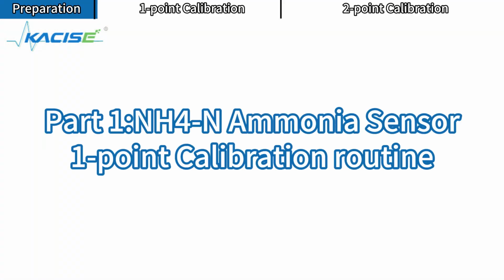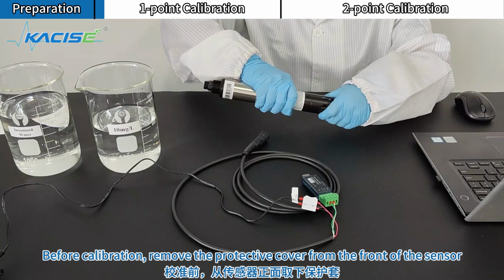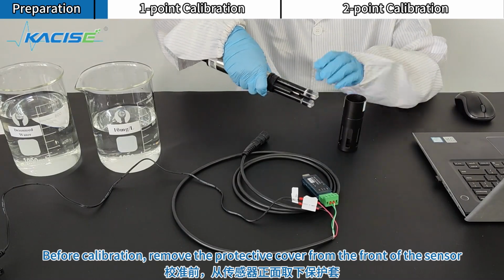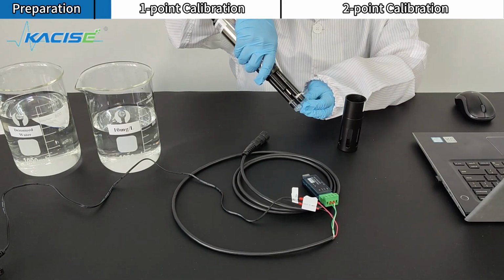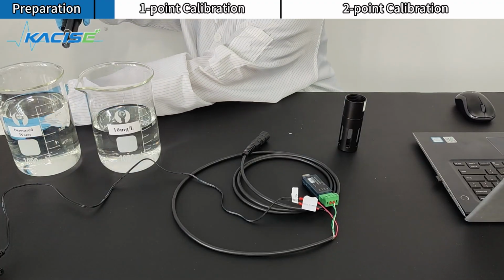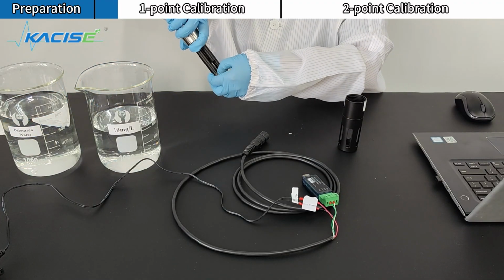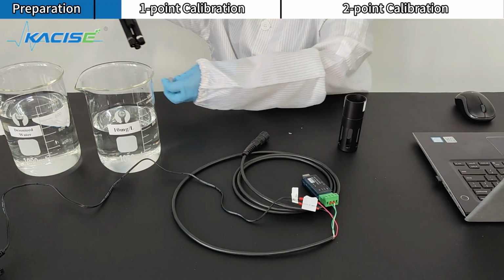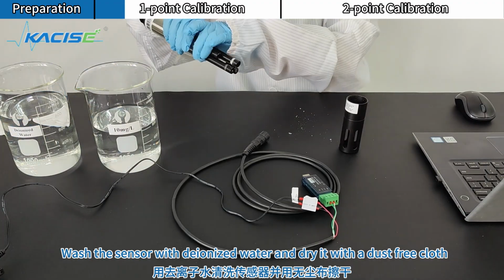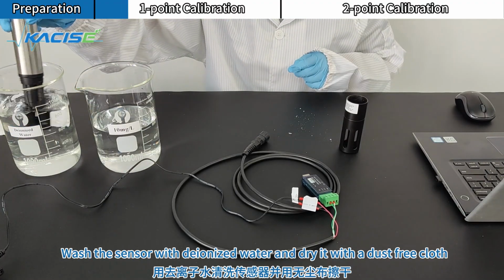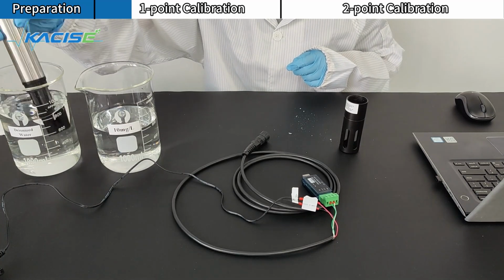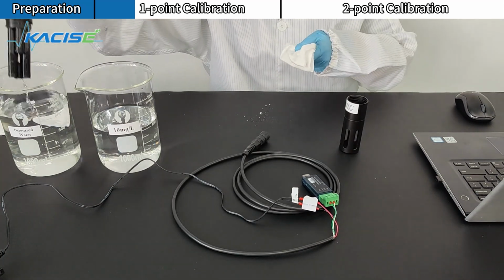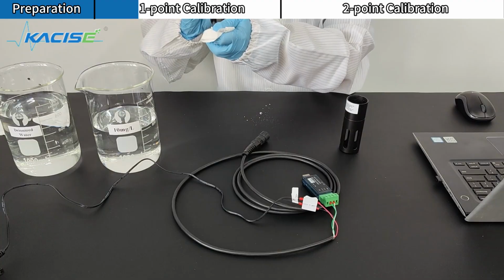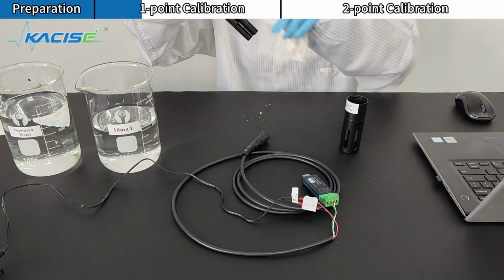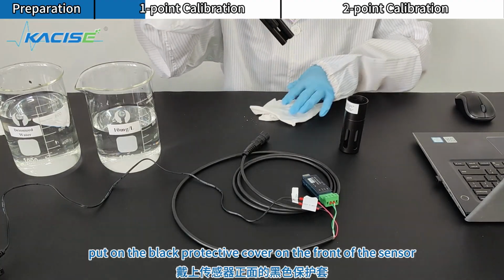Part 1, NH₄-N Ammonia sensor. 1-point calibration routine. Before calibration, remove the protective cover from the front of the sensor. Wash the sensor with deionized water and dry it with a dust-free cloth. Put on the black protective cover on the front of the sensor.